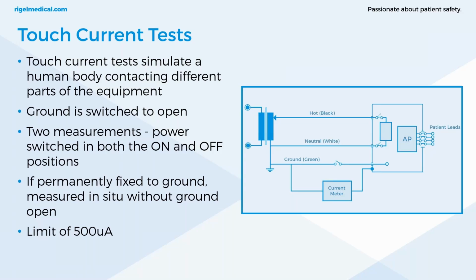Touch current tests simulate a human body coming into contact with different parts of equipment. The measured leakage current values are compared with acceptable limits. Two measurements again are taken, both in the on and off positions. Only one measurement is taken if a switch is not supplied.